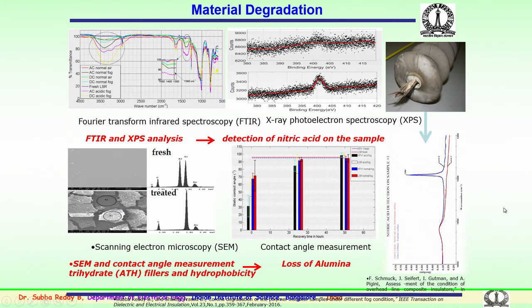So, the material degradation is very important. I was mentioning the surface studies, various morphological studies which are being carried out on the surface after continuously applying the corona moisture or the acidic fog effect. The samples over a period of time after the experimentation are taken out carefully, and these have to be verified. The surface changes, or surface morphological happenings, have to be properly analyzed.